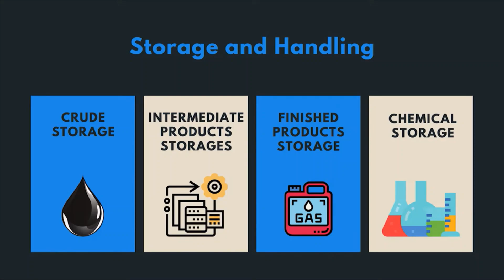Whenever product is received in the storage tanks, the level will go up. The hydrocarbon vapor is always on top of the liquid surface, and these vapors go out while air comes in during pumping in and pumping out operations. So during this process, there's a small quantity of hydrocarbon lost as evaporation. This kind of tank is primarily meant for non-volatile products like finished lube oil or fuel oil, mainly heavy oils. If I use a cone roof or fixed roof tank for a lighter hydrocarbon, there is always a possibility of vapors going out continuously, causing huge evaporation loss.